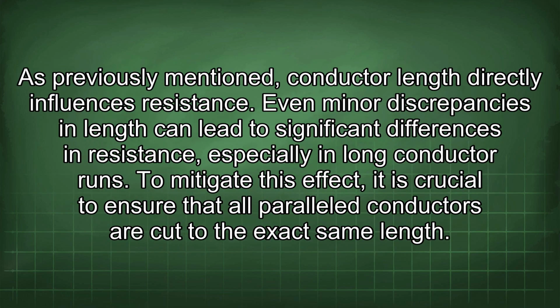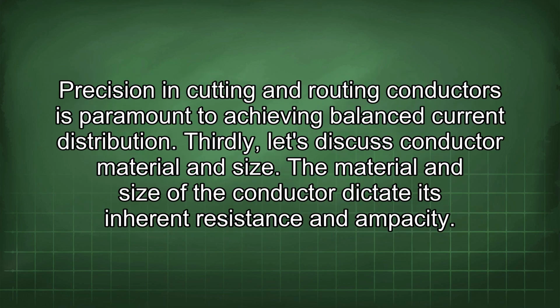As previously mentioned, conductor length directly influences resistance. Even minor discrepancies in length can lead to significant differences in resistance, especially in long conductor runs. To mitigate this effect, it is crucial to ensure that all parallel conductors are cut to the exact same length. Precision in cutting and routing conductors is paramount to achieving balanced current distribution.